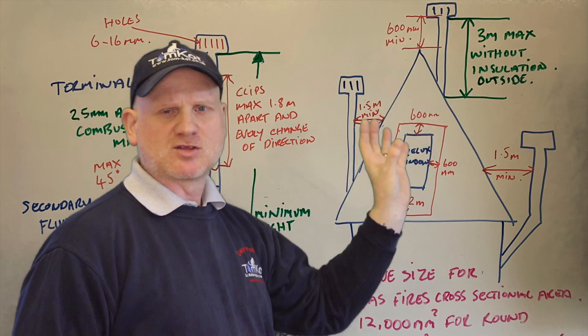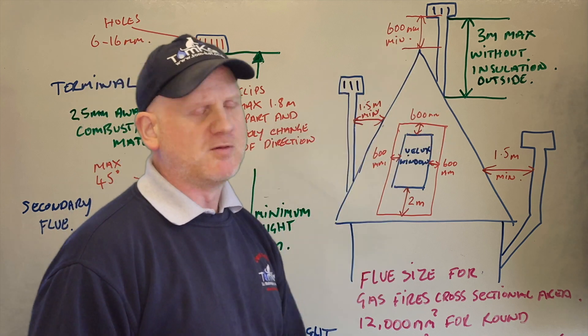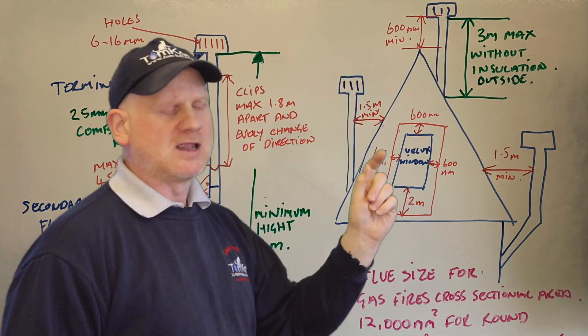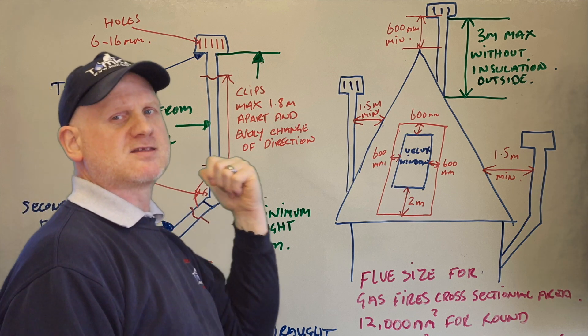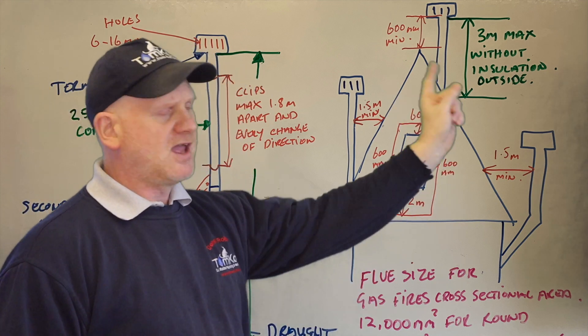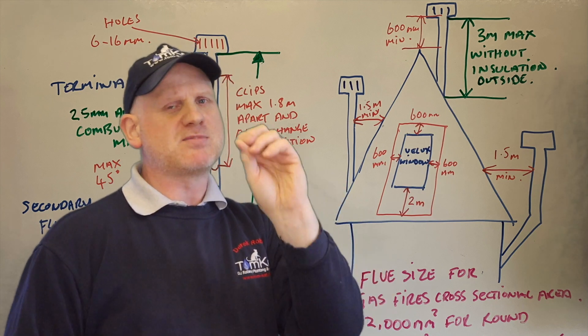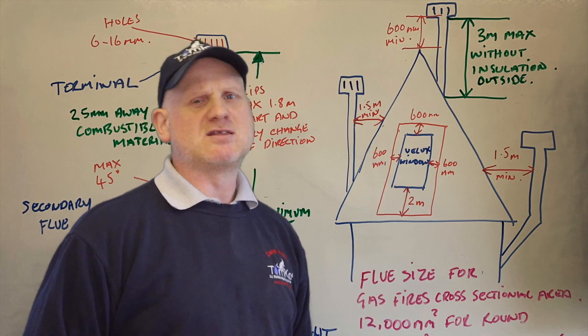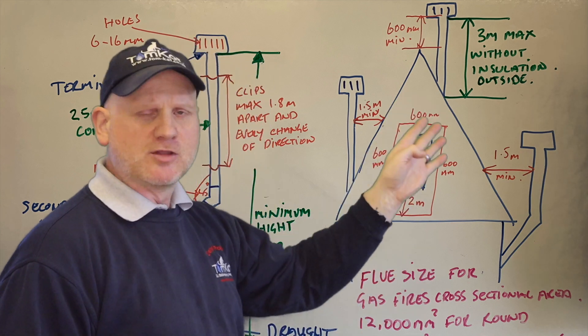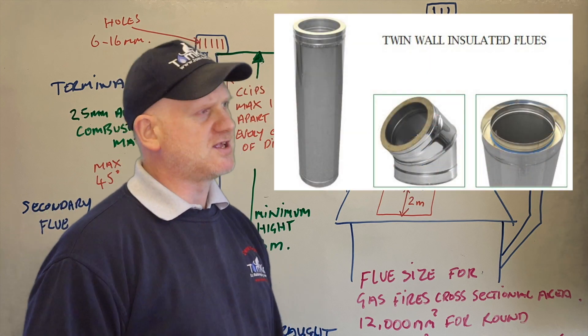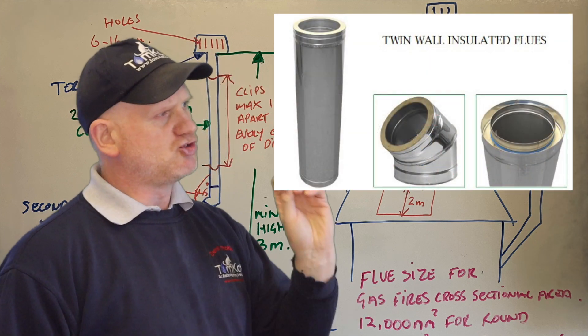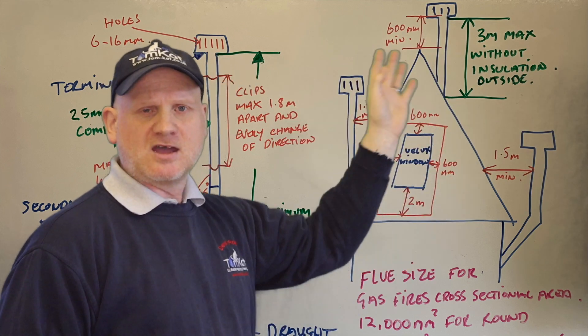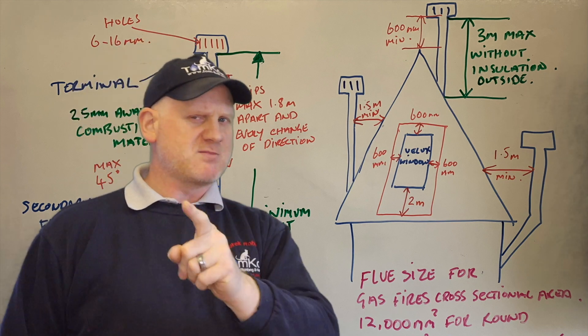Those are the main things to look out for when open flue appliances exit through the roof. Also, the maximum length you can have outside the property without insulation is three meters. If you've got more than three meters of pipe outside, it must be insulated twin wall pipe — not just relying on the air gap of the twin wall.